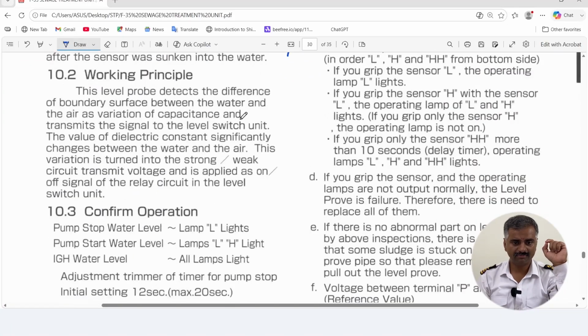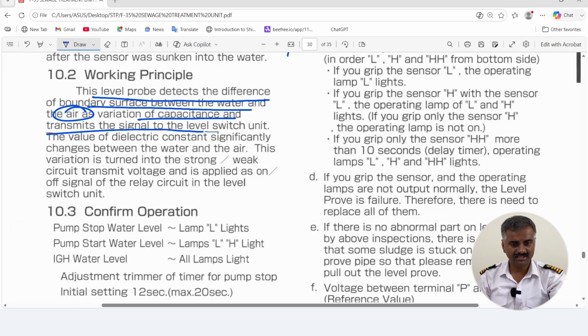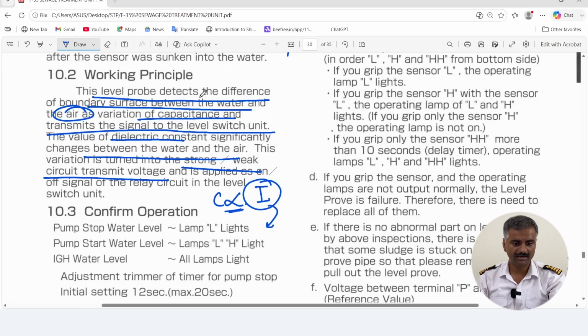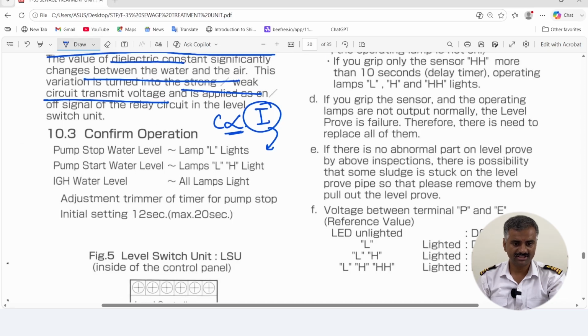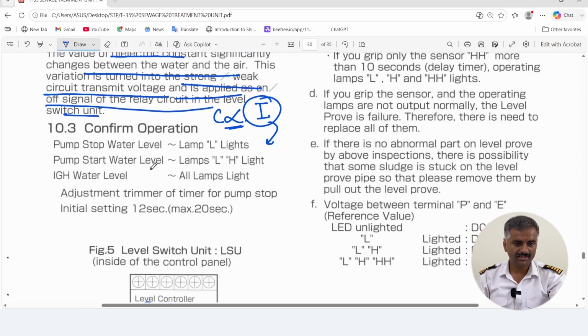So the working principles we have already talked about. The water level probe detects the difference in the boundary surface between the water and the air, and capacitance varies. As the capacitance varies, the transmitting signal changes to the level switch unit. The value of the dielectric constant changes significantly between water and air, and this variation is turned into a strong or weak circuit transmit voltage. As this changes, capacitance changes and the current value changes, and it reaches the control panel, and a different current value is reaching there. As the change in current occurs, the same is applied as the signal to the relay circuit in the level switch unit.